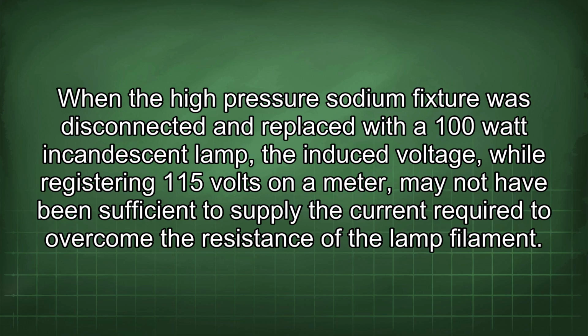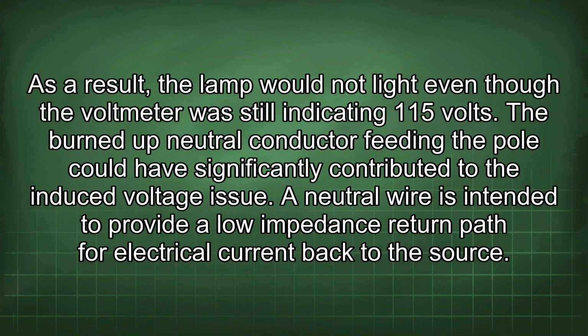When the high-pressure sodium fixture was disconnected and replaced with a 100-watt incandescent lamp, the induced voltage, while registering 115 volts on a meter, may not have been sufficient to supply the current required to overcome the resistance of the lamp filament. As a result, the lamp would not light even though the voltmeter was still indicating 115 volts.